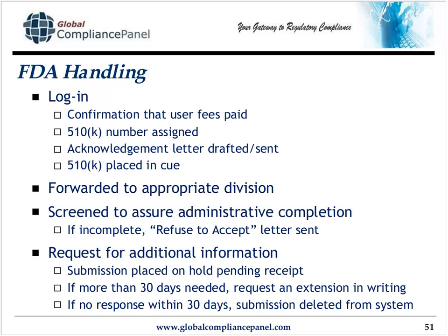After this, they will review the document and request additional information. In the meantime of their reviewing, while they're waiting for this, they're going to give you 30 days, but they're going to put your submission on hold. And if you need more than 30 days, you've got to request an extension in writing.